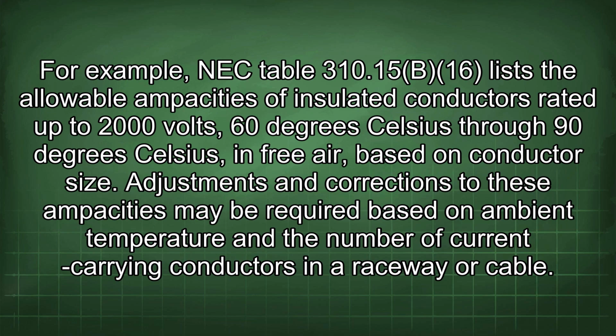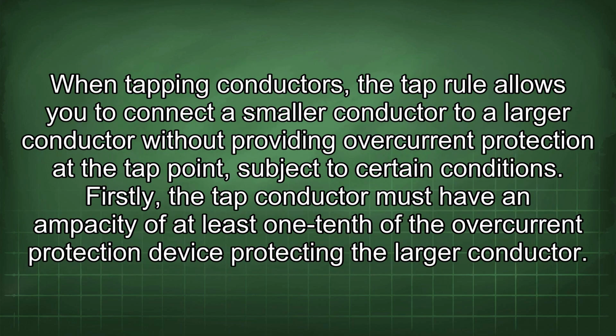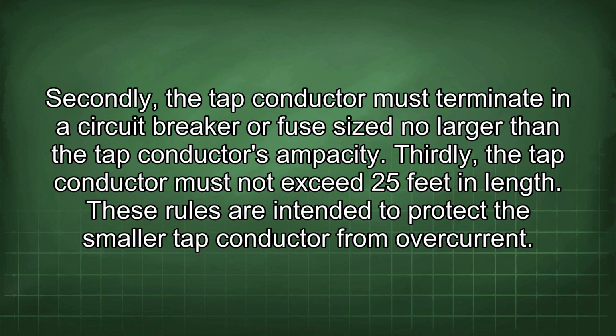Adjustments and corrections to these ampacities may be required based on ambient temperature and the number of current-carrying conductors in a raceway or cable. When tapping conductors, the tap rule allows you to connect a smaller conductor to a larger conductor without providing overcurrent protection at the tap point, subject to certain conditions. Firstly, the tap conductor must have an ampacity of at least 1/10 of the overcurrent protection device protecting the larger conductor. Secondly, the tap conductor must terminate in a circuit breaker or fuse size no larger than the tap conductor's ampacity. Thirdly, the tap conductor must not exceed 25 feet in length. These rules are intended to protect the smaller tap conductor from overcurrent.